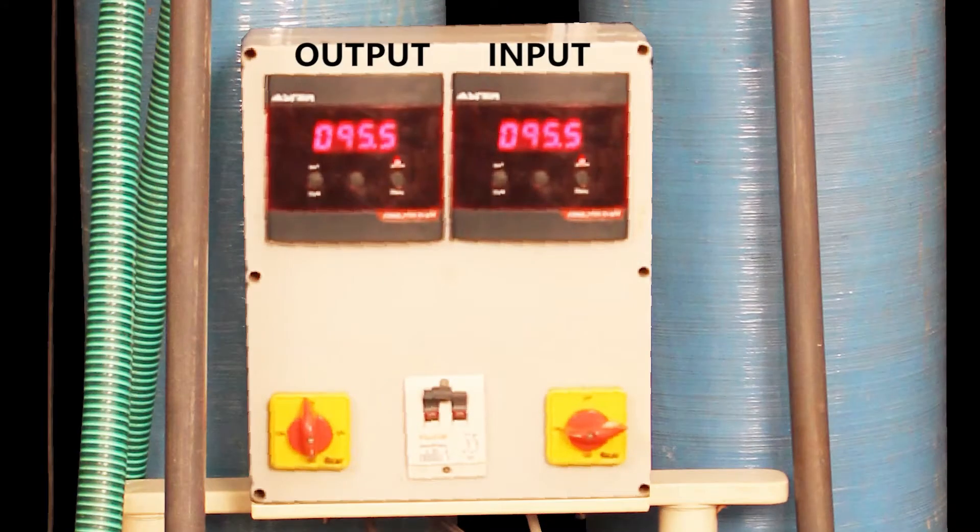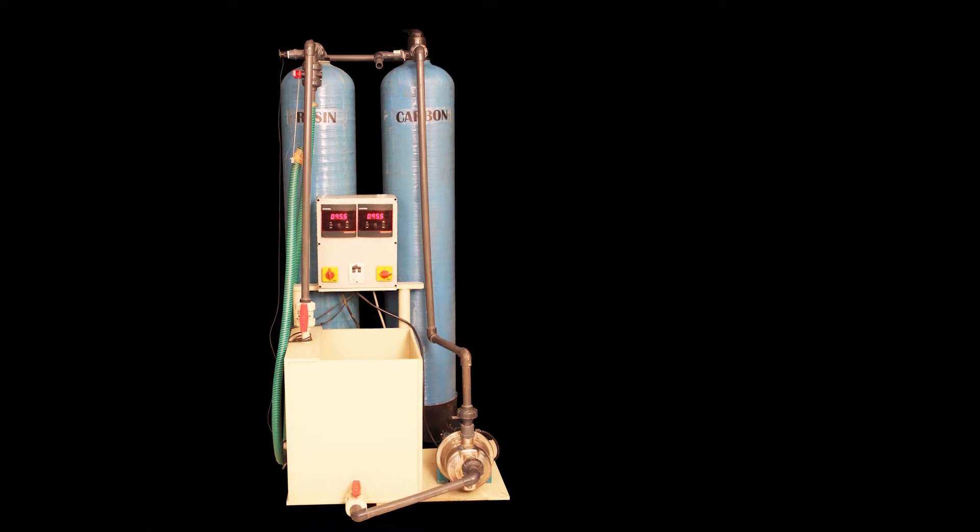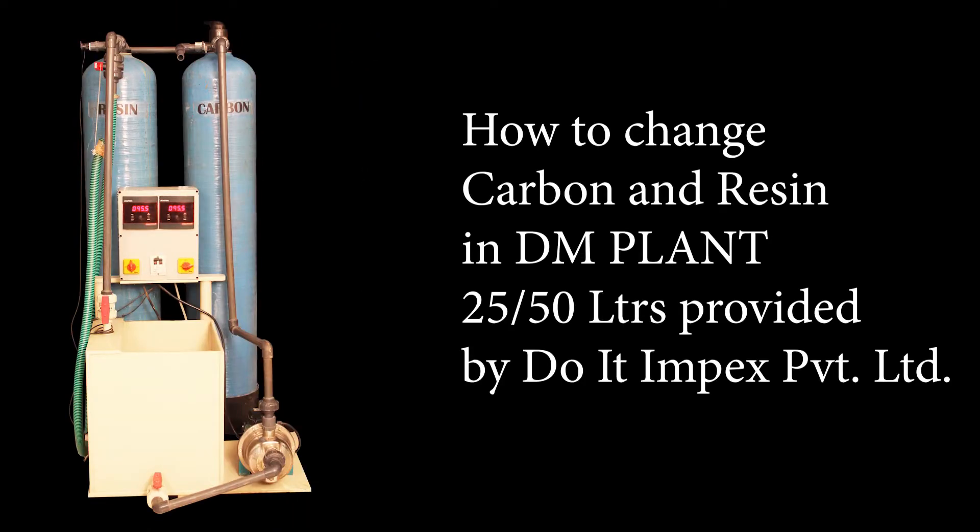A DM plant produces DM water around 0 TDS. If your TDS meter shows a reading above 20, then you will need to change carbon and resin. In this video we will show you how to change carbon and resin in a DM plant.